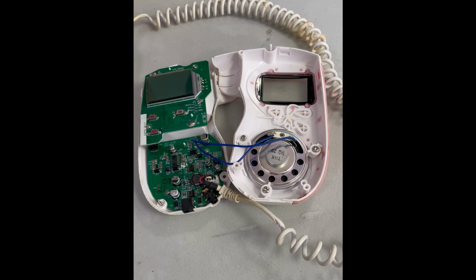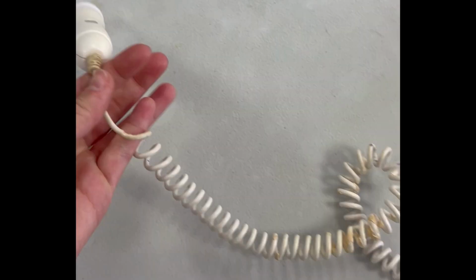Since this device has two primary components, it's important to ensure a good connection between the two. Some versions of the device may allow for disconnection of the probe from the base unit of the device. If there's an issue, check to make sure that these connections are maintained and crack-free and undamaged. If the cable can be replaced, this would be an easy way to repair issues localized to the connection. If there is visible damage to the cord, it may be helpful to apply electrical tape.